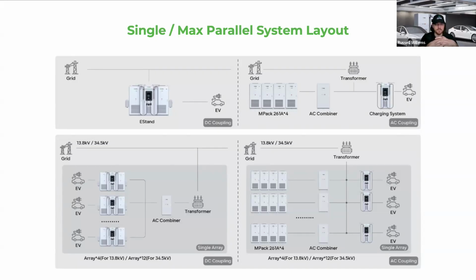You can also use an AC combiner when connecting directly to the high voltage grid, to bring that down through a transformer to 480, then into an AC combiner that distributes and charges a wide number of the EStand modules. So there are standalone easy integrations for existing commercial energy levels, separating them from the charger, and tying into potentially new infrastructure.